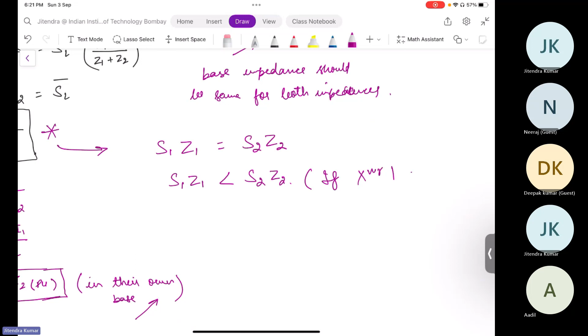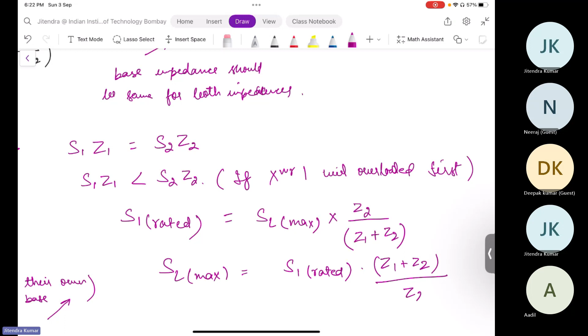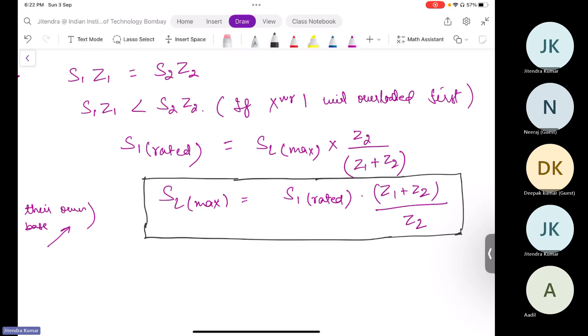We can calculate S1 rated. The contribution of transformer 1 would be SL max, let us assume some maximum amount of load that could be catered, into Z2 divided by Z1 plus Z2. From this expression, you can get the expression of maximum loading: SL max is equal to S1 rated into Z1 plus Z2 divided by Z2. This expression determines the limit of the load that could be catered from the lower rating transformer. Is it clear till this point?